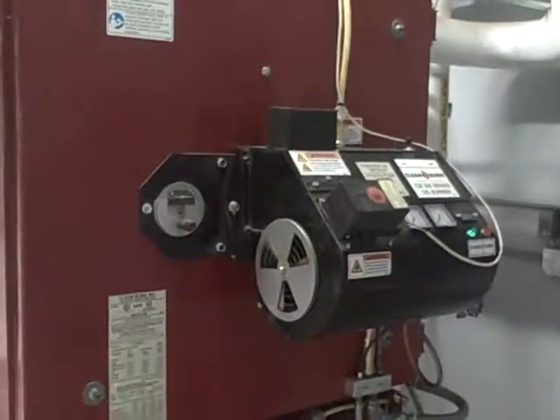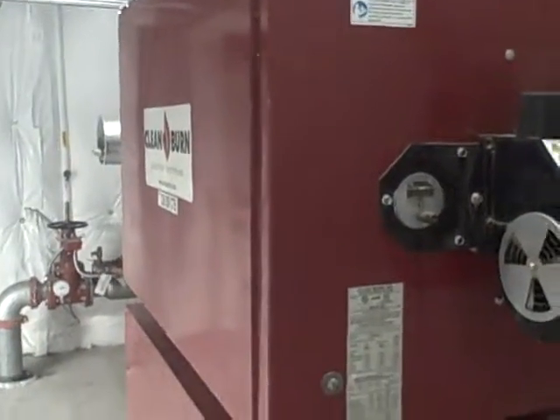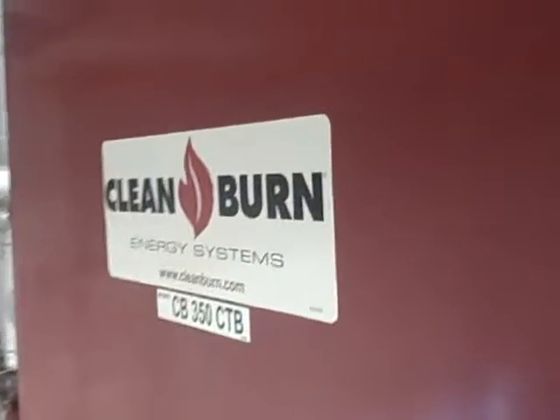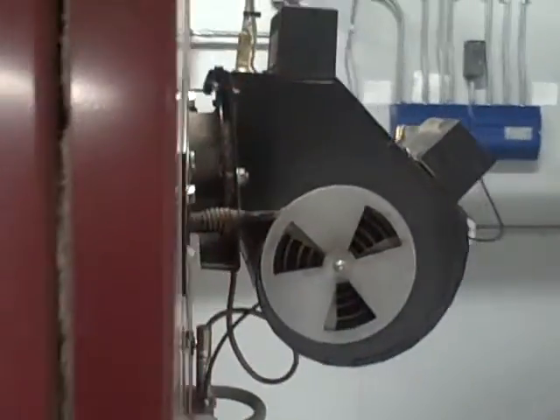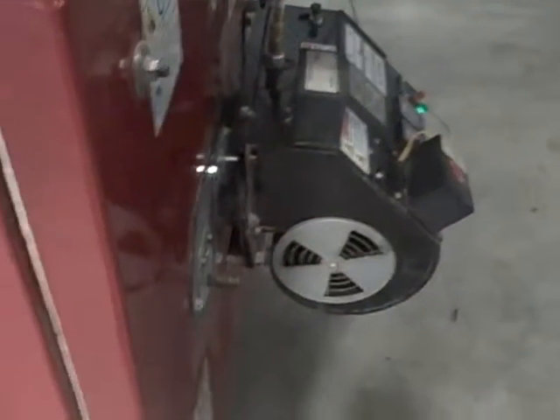Okay, we're up where these boilers are at. I've got two of them. They're 350,000 BTU clean burn units. They can run together, but they'll run in sequence. We'll run the upper unit 40 hours, and then it automatically slips down to the lower unit. These things are good for about 20,000 hours before you rebuild them.